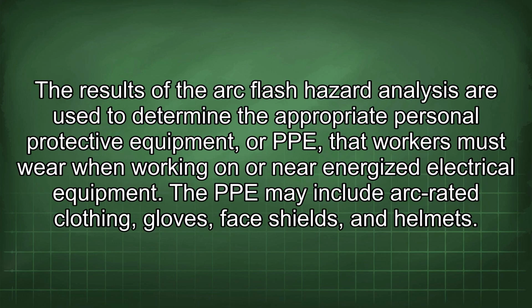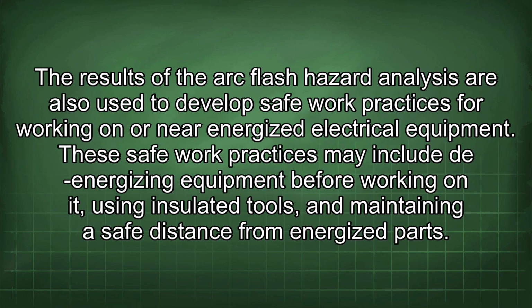The results of the arc flash hazard analysis are used to determine the appropriate personal protective equipment, or PPE, that workers must wear when working on or near energized electrical equipment. The PPE may include arc-rated clothing, gloves, face shields, and helmets. The results are also used to develop safe work practices for working on or near energized electrical equipment. These safe work practices may include de-energizing equipment before working on it, using insulated tools, and maintaining a safe distance from energized parts.